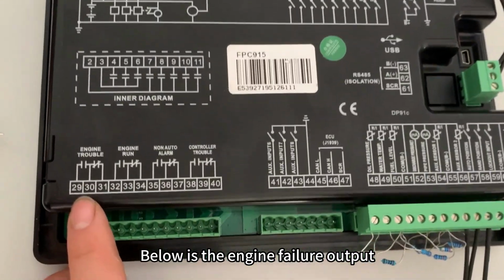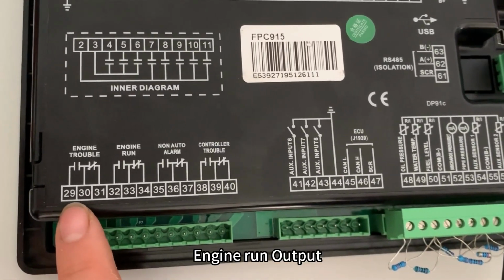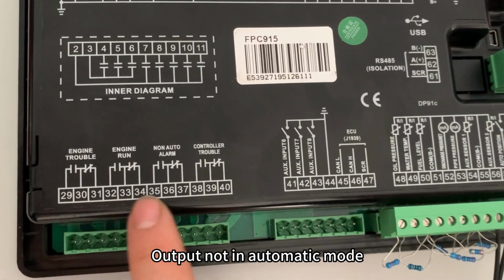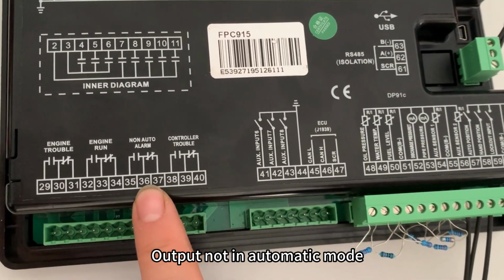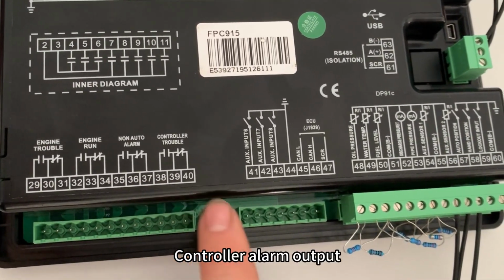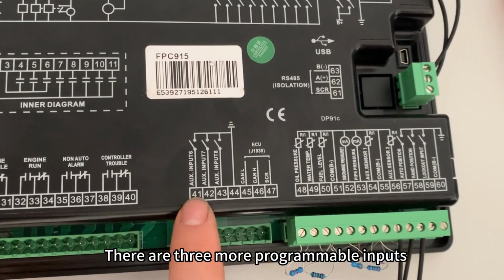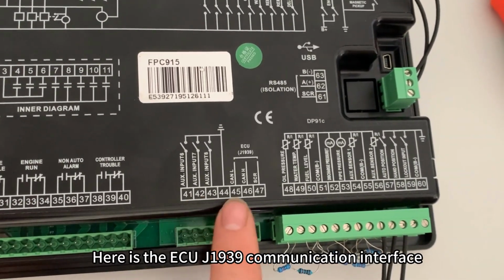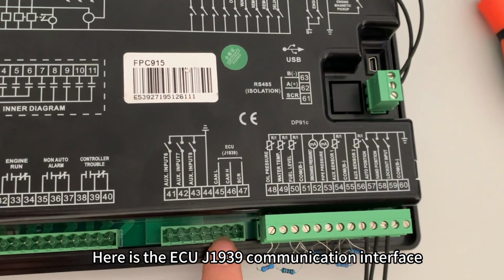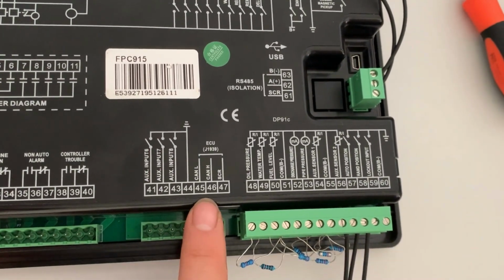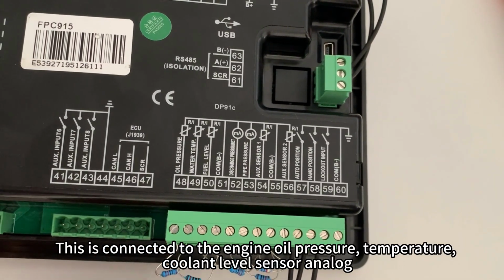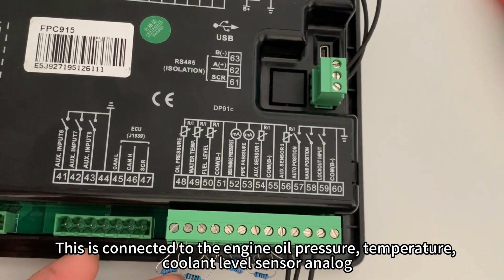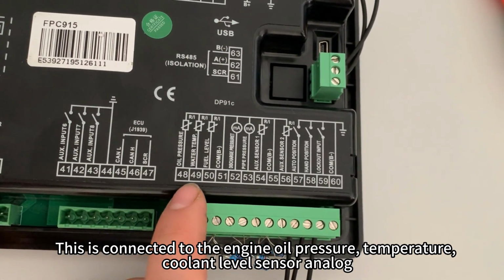Below is the engine failure output. Engine run output. Output not in automatic mode. Controller alarm output. There are 3 more programmable inputs. Here is the ECU J1939 communication interface. This is connected to the engine oil pressure, temperature, and coolant level analog sensors.